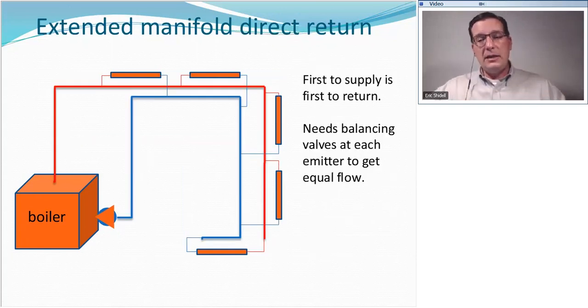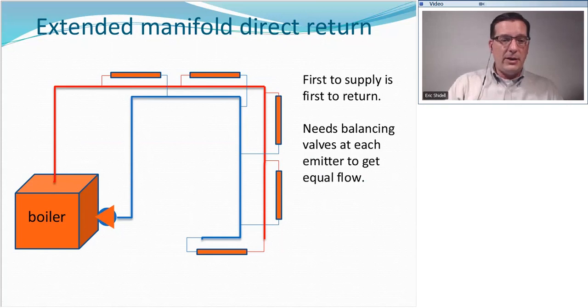As we get larger into bigger systems, we get bigger piping. We get more expensive. This is called the extended manifold direct return, where we have a supply leaving the boiler and pretty much going all the way down the building to the very, very end. And then another main pipe beginning at that end and coming all the way back to the boiler. Piped in between are the branch lines. So here's one branch coming back in. Here's another branch coming back into the return.